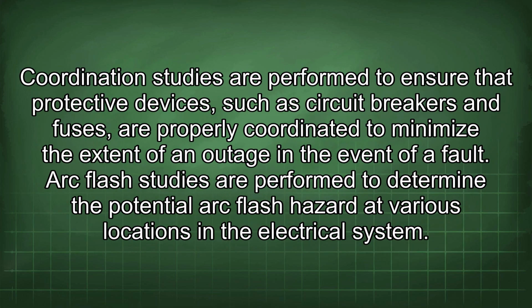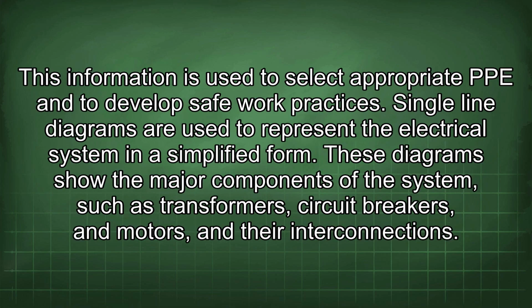Coordination studies are performed to ensure that protective devices, such as circuit breakers and fuses, are properly coordinated to minimize the extent of an outage in the event of a fault. Arc flash studies are performed to determine the potential arc flash hazard at various locations in the electrical system. This information is used to select appropriate PPE and to develop safe work practices.